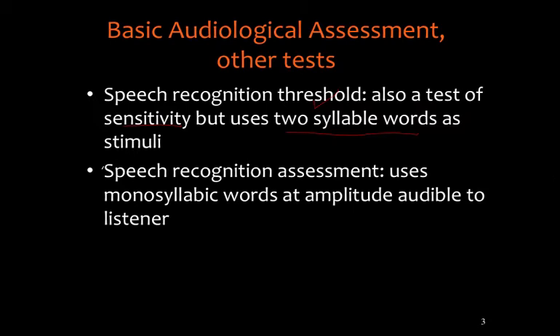There is a second type of speech recognition test using monosyllabic words. The distinction here is that the amplitude is set at a level at which the words are audible to the listener, and then it's a test of understanding. Speech recognition threshold is measured in decibels, while speech recognition with monosyllabic words — sometimes called speech discrimination, though that's not psychometrically correct — generates a percent correct score, where 100% would be a perfect score. This test is used to address the person's word understanding ability.